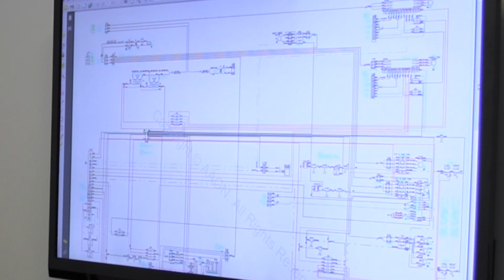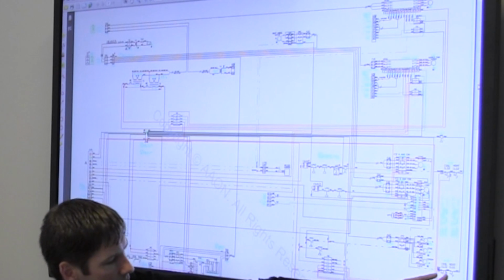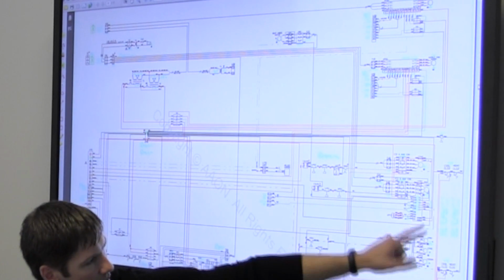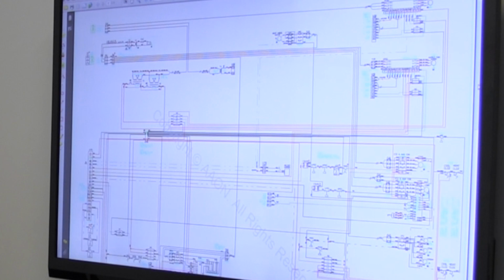but depending on how it's controlled, there's timers and anti-recycle timers. There's various things that will hold that compressor off when it thinks it should be on. And all that light is doing is saying, half of me wants to run, but something else is telling me I can't. Maybe the airflow hasn't made yet. Maybe the timer just hasn't cycled through yet. And so there's other components that'll cause that little red light to blink, and it's not necessarily an alarm. Here's your outside air temperature lockouts to lock out the compressor for heating or cooling. But just a standard wiring diagram.